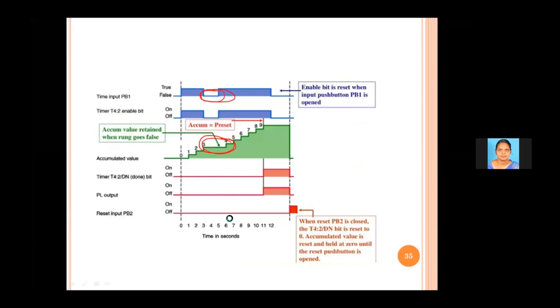Normal retentive timers are used similar to the normal timer. In this case, the pressure switch is used. Whenever the switch goes to the on state, the enable will be activated. After a preset value of 60, to give a delay of 60 seconds, the time base should be 1.0. Then the horn coil will be energized, and the horn will be activated in the output.